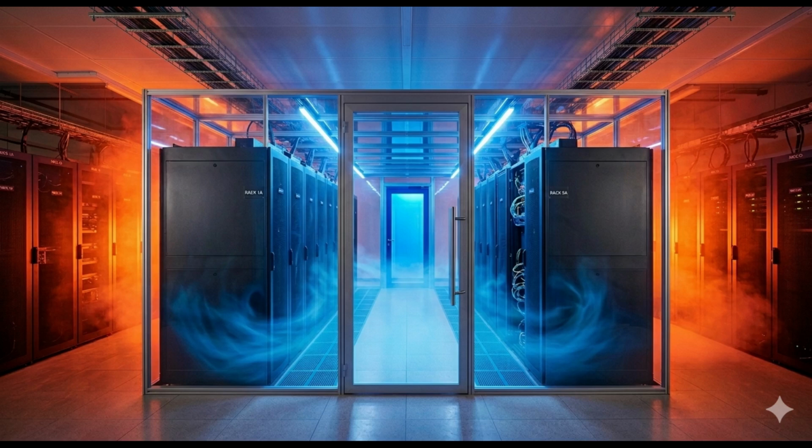You achieve this by having multiple supply paths, usually one active path and one passive path. So you can seamlessly switch over. Right. And this topology can typically tolerate around 72 hours of a municipal power outage using backup systems. Availability jumps to 99.98%. So we went from 22 hours of downtime down to, what is that? About 1.6 hours annually. Okay, massive jump.